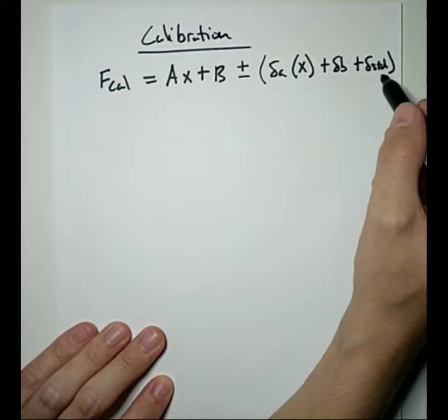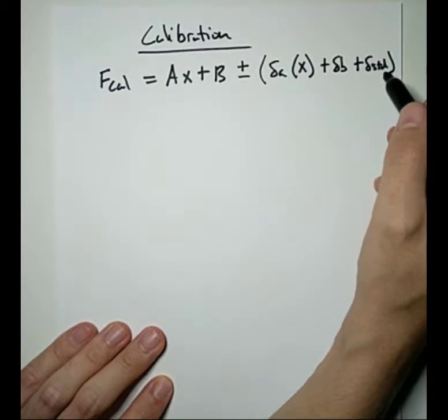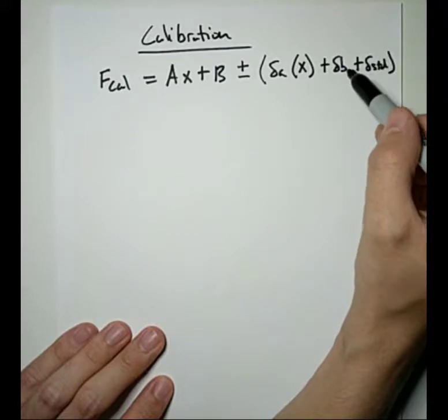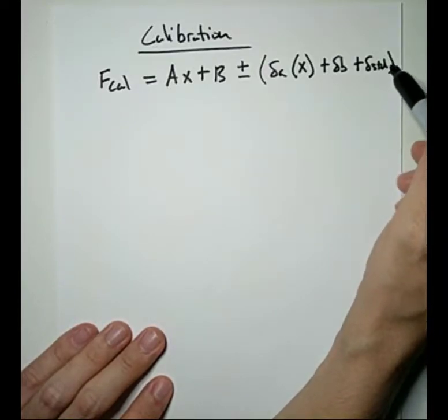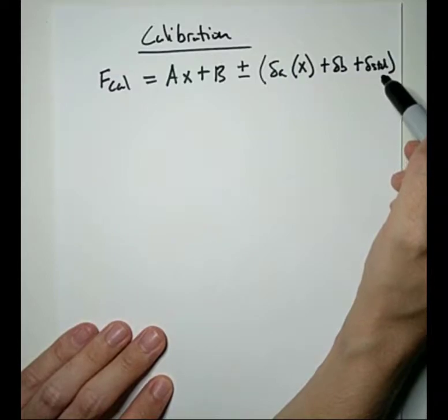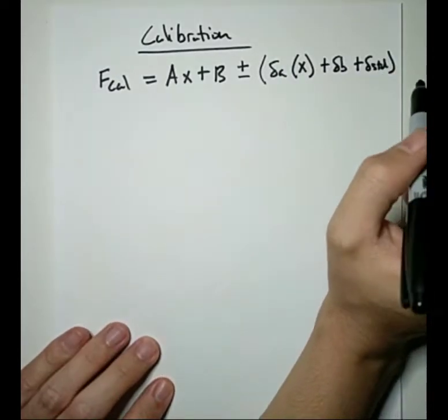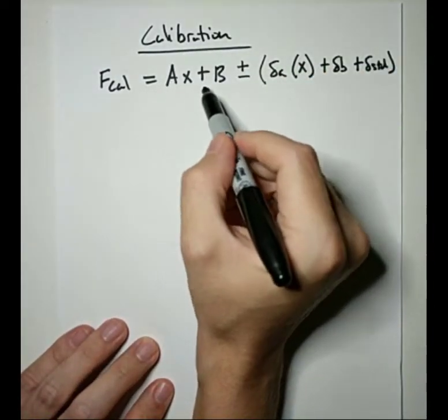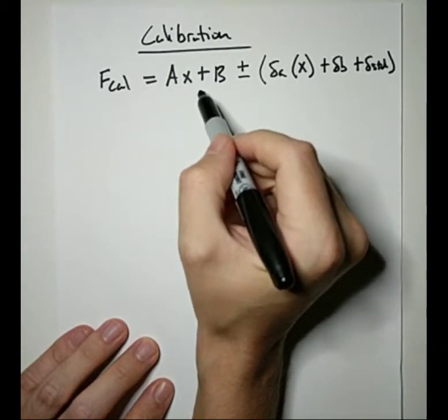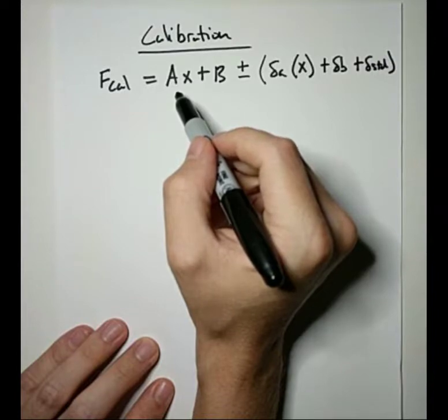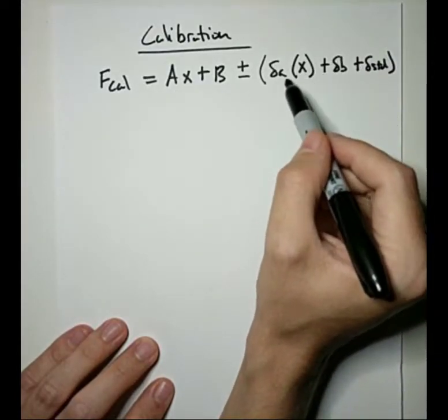So for both of the calibration equations you make, you'll have one for the rotometer and one for the vortex shedding meter. Del standard is going to be the uncertainty of the magnetic inductance meter. It is always the uncertainty of the sensor you used as a standard in the calibration. So this will be how we perform the direct calibration part, and then this will be the uncertainty analysis.